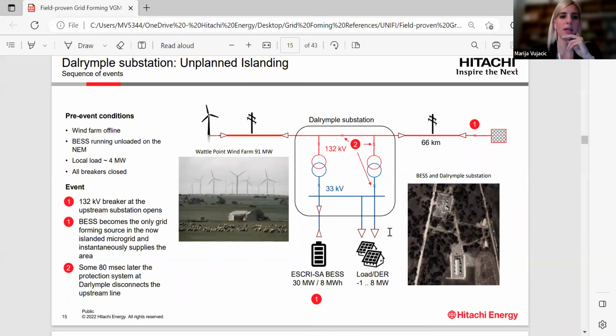Then, during the commissioning, this unplanned islanding was demonstrated. So at instant 1, the 132 kV breaker at the upstream substation opened. I think it is important to mention that in this first case the wind farm was offline. So BESS was running unloaded, and at this first moment, when the breaker opened, BESS became the only grid forming source in the now islanded microgrid, and instantaneously supplied the area. Some 80 milliseconds later, the protection system at the substation disconnected the upstream line, and ESCRI-SA BESS continued supplying the load.